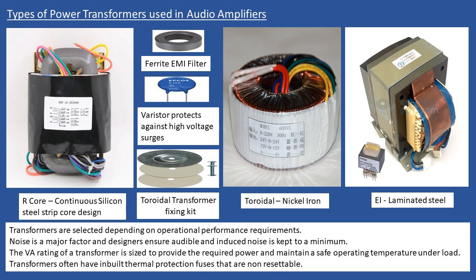So what the video shows is something which we call a ferrite ring or an electromagnetic interference filter, and these are very common. And really what it consists of is a ferrite core, or it could be a ferrite ring as we're showing here, and the mains power cable to the amplifier would pass through the ring, and then what you would have is maybe 3 or 4 turns, and then it goes off to the power switch. Very common. Or you may have one which is integral built. If it's a cable which is directly connected to the amplifier, you don't have to plug it and unplug it, and it may look like a bobbin.